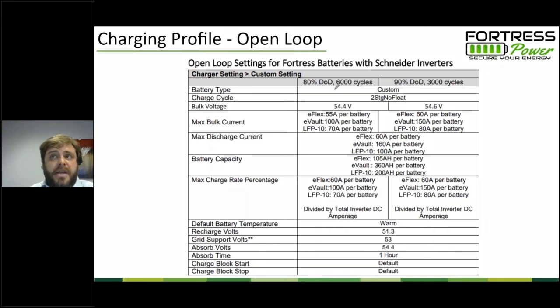Now, our batteries, and this is going to vary from one lithium chemistry to another, and maybe even within the same chemistry from one manufacturer to another, depending on how the internal battery cells are wired together. But for our batteries, we're all at a 54.4 volt charging voltage, whether you're applying a constant aggressive charge at high amperage in bulk, or a lower amperage charge at the same voltage with absorb. We're pretty much at 54.4 volts regardless of the charging cycle.